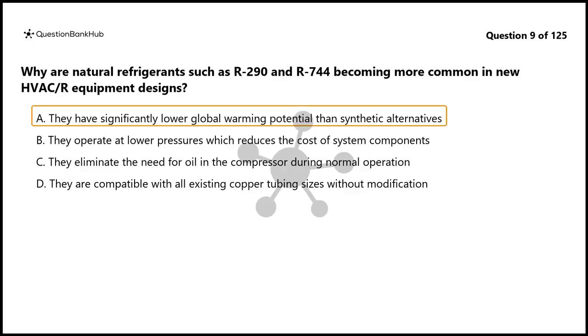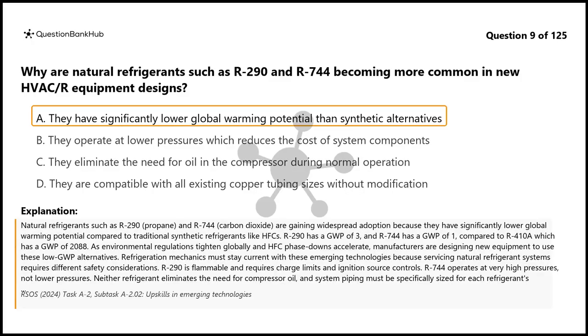The correct answer is A. Natural refrigerants such as R290 propane and R744 carbon dioxide are gaining widespread adoption because they have significantly lower global warming potential compared to traditional synthetic refrigerants like HFCs. R290 has a GWP of 3, and R744 has a GWP of 1, compared to R410A which has a GWP of 2088. As environmental regulations tighten globally and HFC phase-downs accelerate, manufacturers are designing new equipment to use these low GWP alternatives.